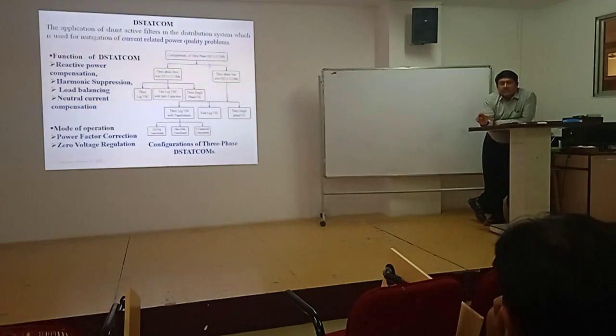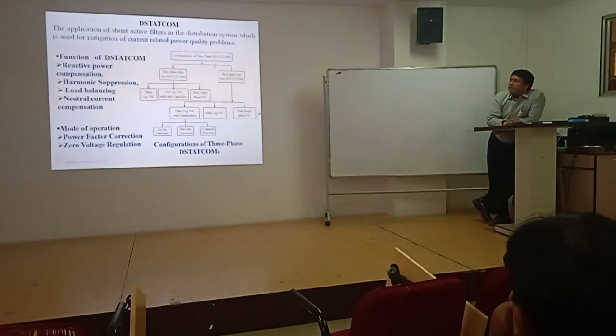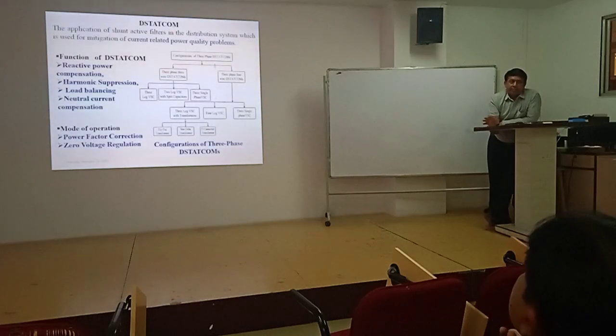If we are going to use this device in a distribution network, and the same device with less switching frequency we are going to use in a transmission network, then it is known as the STATCOM, you can say. Here DSTATCOM and STATCOM, the major change is in switching frequency only. In this case, we are going to take a switching frequency near 10 to 5 kHz, or maybe medium switching frequency. But in case of high-power devices, STATCOM, we are going to take a switching frequency near the fundamental: 1 kHz, 500 Hz, maybe 300 Hz, depending upon the design.